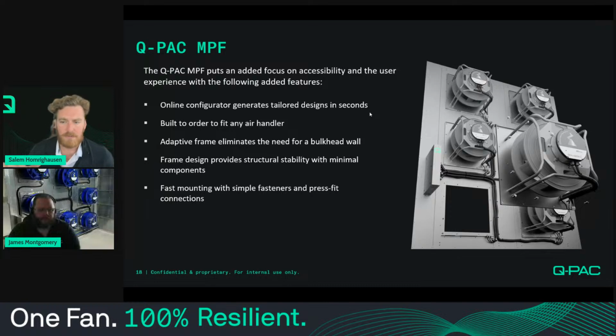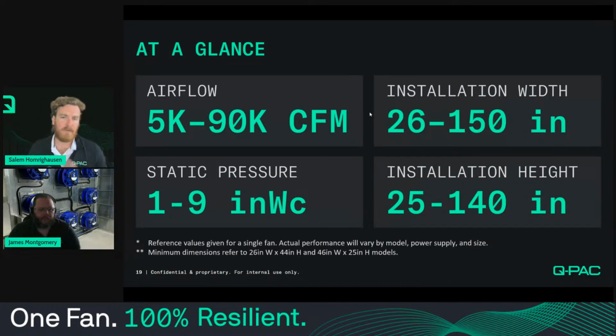Before we go any further, I want to give you a quick idea of the performance for these products: 5,000 to 90,000 CFM is the airflow performance window for a single multimotor plenum fan, and they can do 1 to 9 inches of total static pressure. So if you're looking at an air handler that's 5,000 CFM or up, and between 1 and 9 inches of total static pressure in water column, then a Q-PAC fan will work for that system.